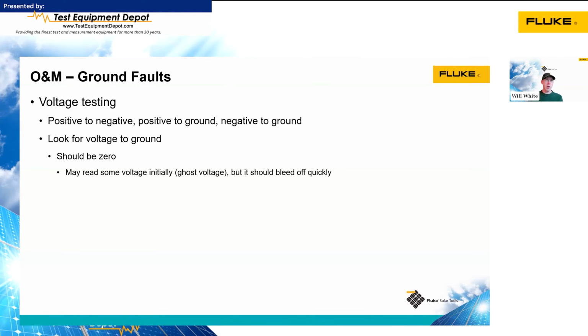So how can we find these ground faults? Voltage testing in a PV circuit can be used, and we'll go through some examples of that. I'm going to measure from the positive to the negative to see what my open circuit voltage is, and then measure from positive to ground and negative to ground. Under normal operating conditions, assuming that there's not a connection to ground in the inverter, measuring positive to ground and negative to ground should come up with 0 volts because there's no potential between those sides and ground.